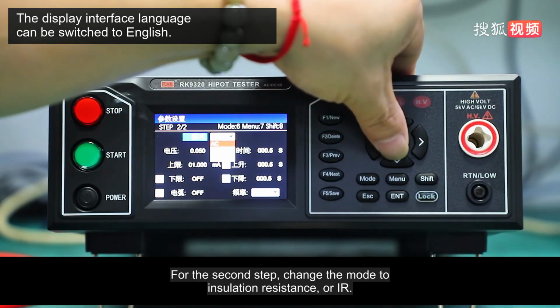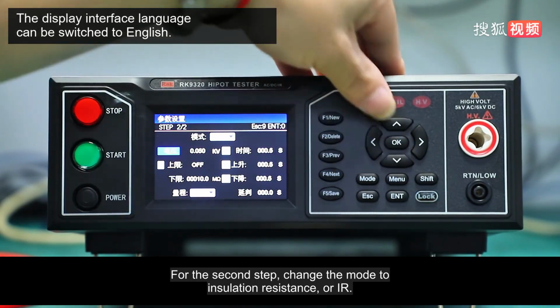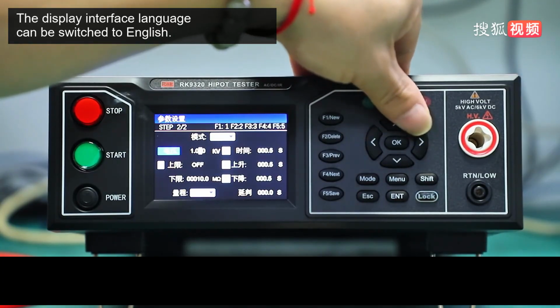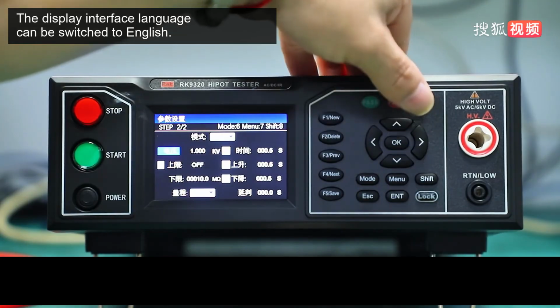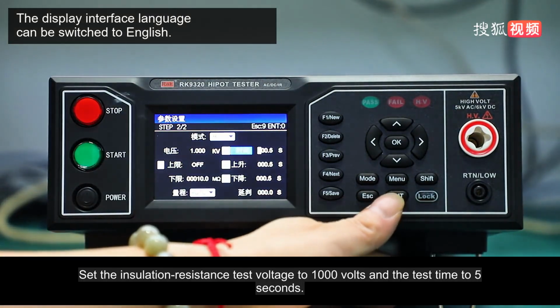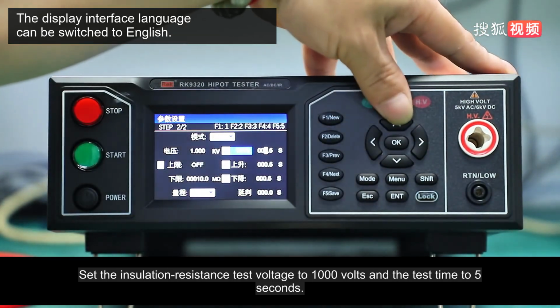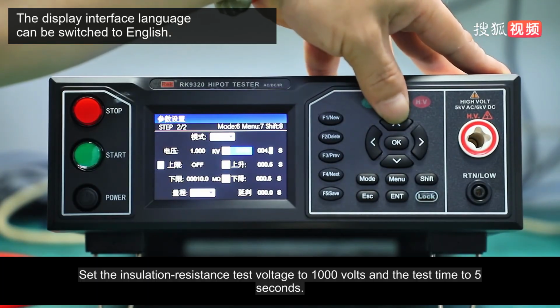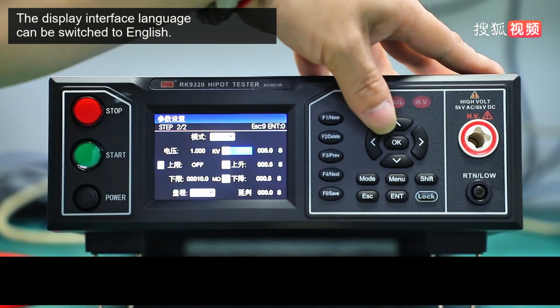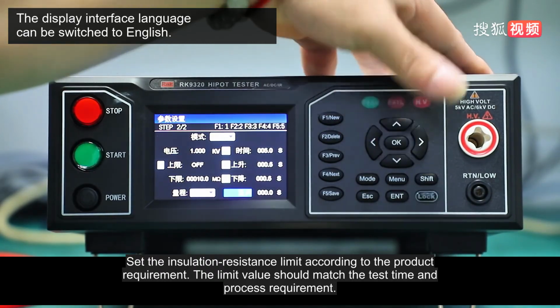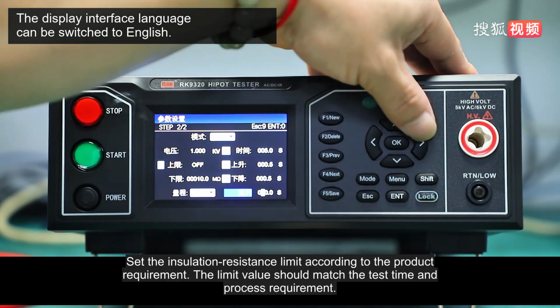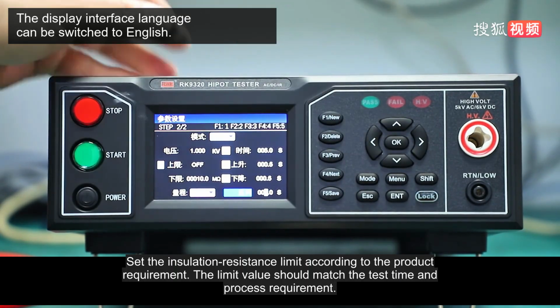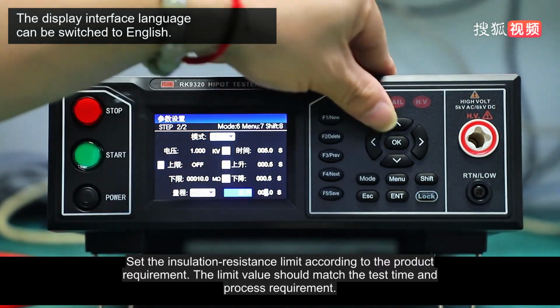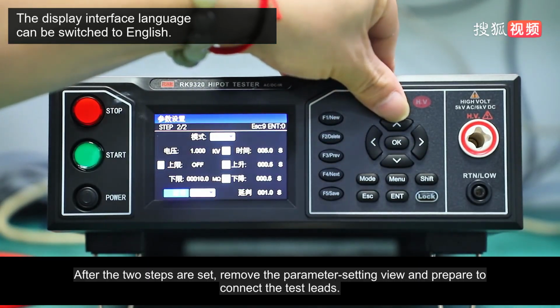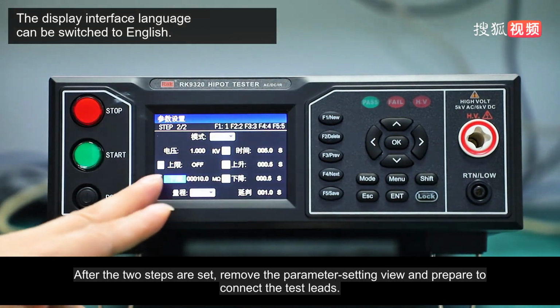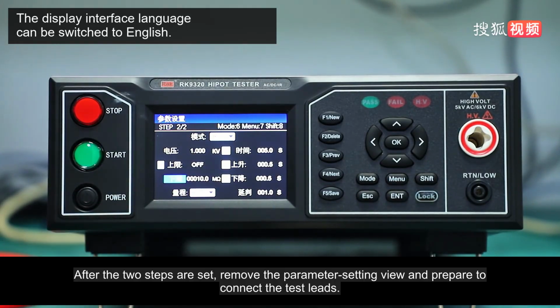For the second step, change the mode to insulation resistance or IR. Set the insulation resistance test voltage to 1000 volts and the test time to 5 seconds. Set the insulation resistance limit according to the product requirement. The limit value should match the test time and process requirement. After the two steps are set, remove the parameter setting view and prepare to connect the test leads.